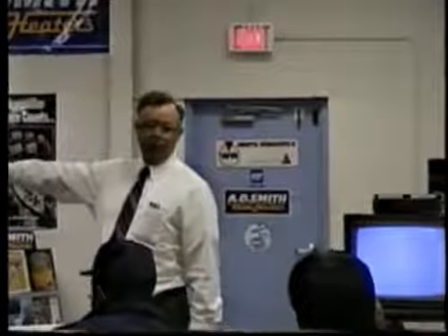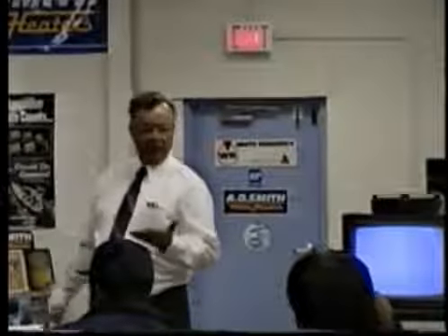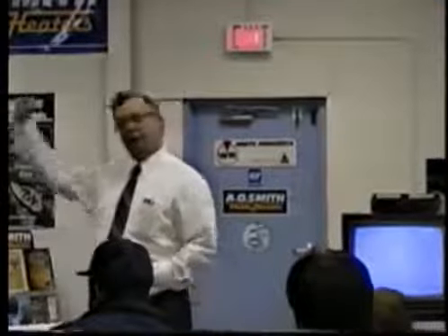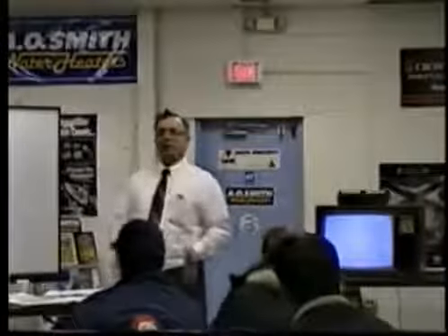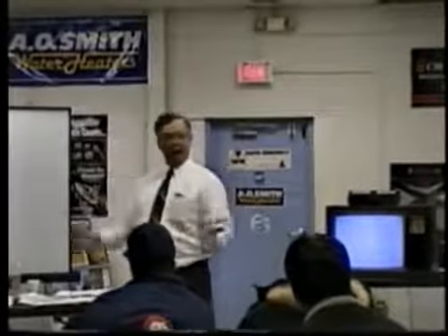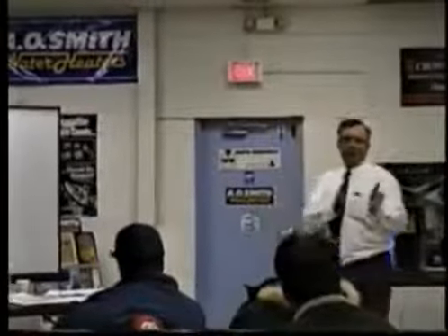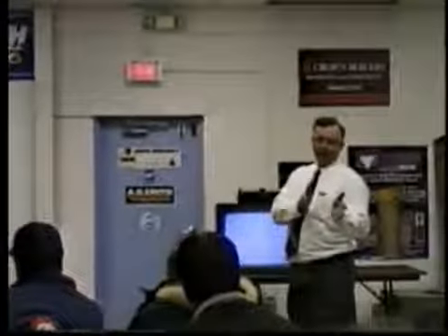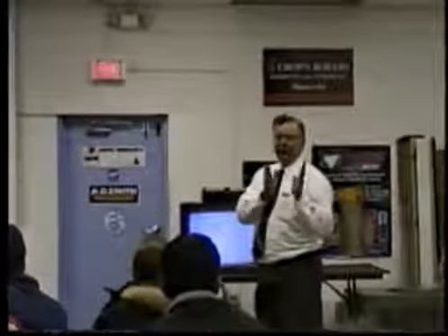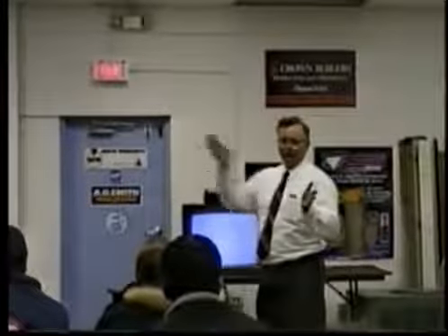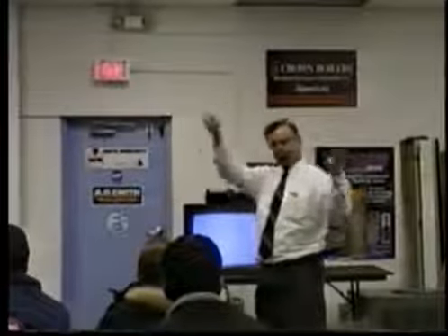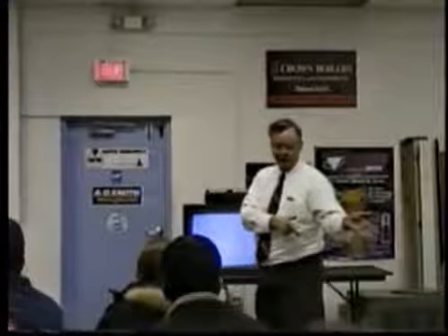But what goes down the drain on a condensing furnace? Water. And on a 20 below zero day, the furnace is running all the time, it's the same question. Gee, how many pints of water go down your drain in a 24-hour period? I don't know, because it's gallons. It's the same thing. Products of combustion, ladies and gentlemen, is CO2 and H2O. You take gas, make fire, oxygen, you get CO2 and H2O.